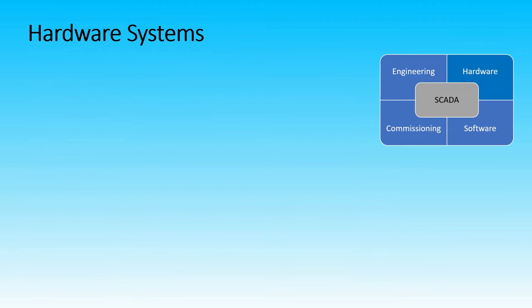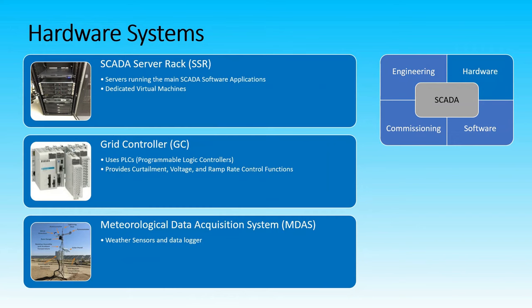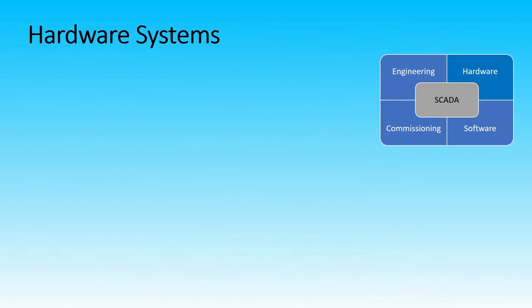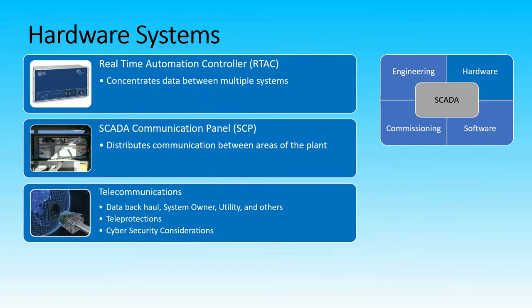When it comes to hardware considerations, a robust SCADA server rack is needed for large PV plants. Virtual machines are more suitable due to their flexibility and manageability. Grid controller PLCs are definitely needed for controls. As for the weather station, there is already a wide range of equipment to choose from. If real-time automation is needed, RTAC is the best way to go. For a large-scale PV plant, distance from the substation building to the inverters out in the field should be considered. This is where fiber line comes into play, terminated through the SCADA communications panel.